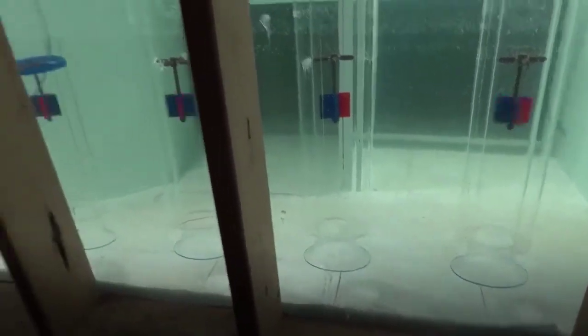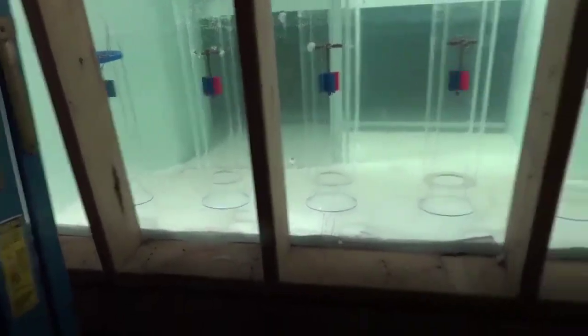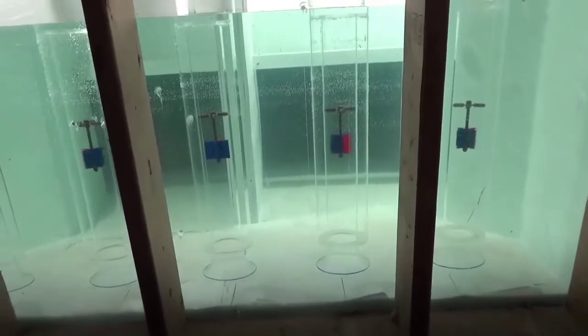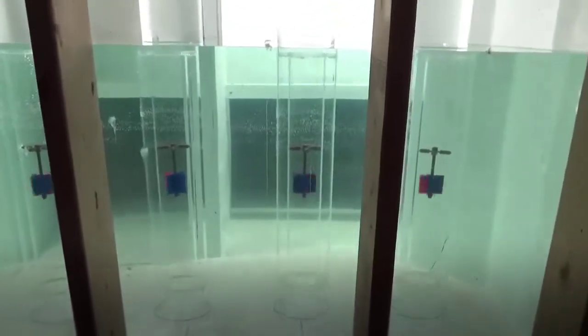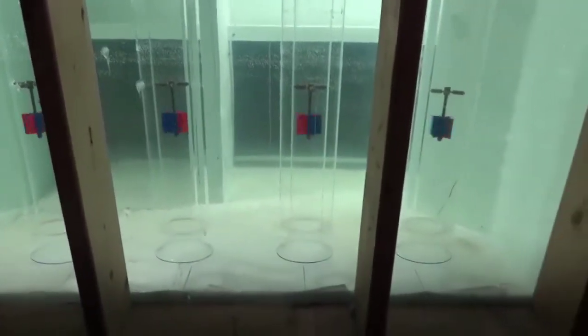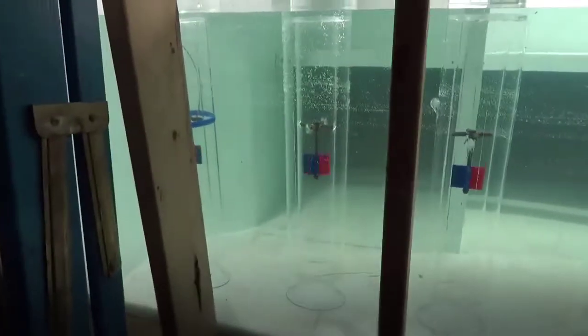This mid-flow vortex activity, there was a good shot right there. It's difficult to get rid of without dividing walls. So flow conditioning baskets are one of the things we're going to be looking at. They do attach to the pump. We've got to make sure that there's adequate screening, which we believe there is, to use those. They'll be very, very effective in this application.